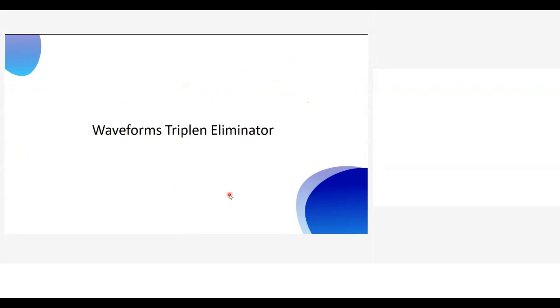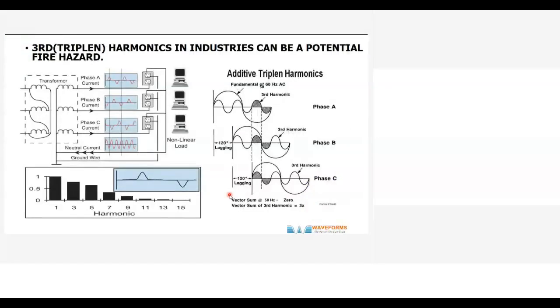So I've spoken from the 5th harmonic to the other harmonics. This 3rd harmonic is a serious issue in many places, especially residential areas or computer data centers, where you install single phase UPS, single phase lighting loads, LED lighting loads, and computers. All of these cause heavy 3rd harmonic.